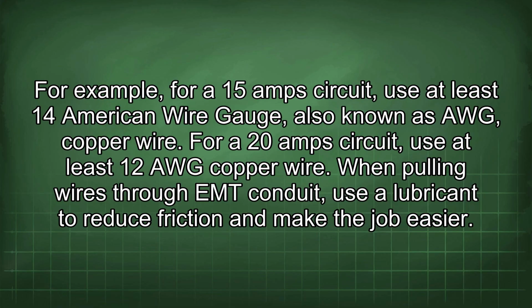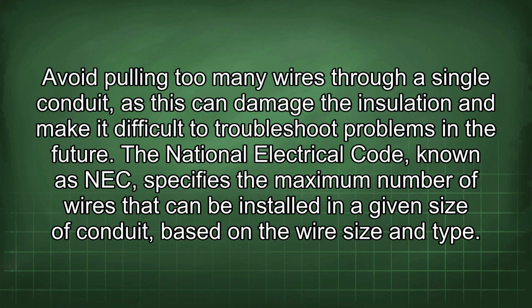When pulling wires through EMT conduit, use a lubricant to reduce friction and make the job easier. Avoid pulling too many wires through a single conduit, as this can damage the insulation and make it difficult to troubleshoot problems in the future. The National Electrical Code, known as NEC, specifies the maximum number of wires that can be installed in a given size of conduit based on the wire size and type.